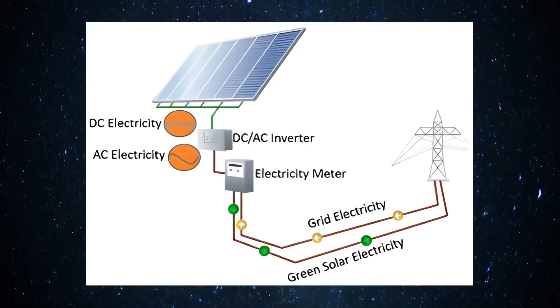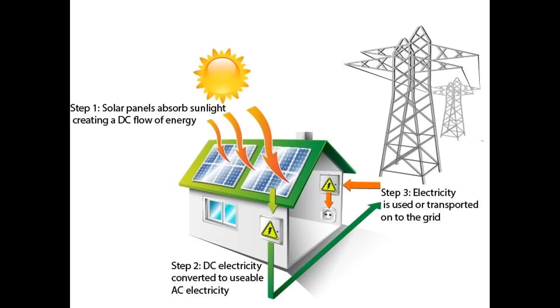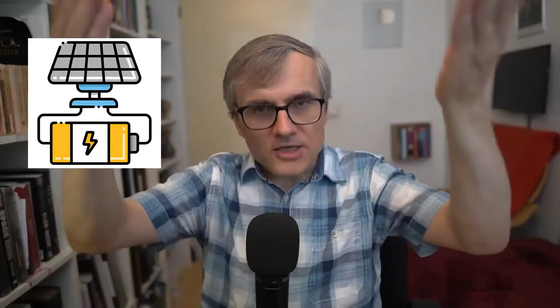In Romania, however, such solutions are expensive. To protect the network, a harsh method is applied, disconnecting the prosumer, if the prosumer, by delivering too much energy into the system, causes the voltage to rise in a dangerous way. The idea is as follows. Any solar panel produces direct current voltage. To feed it into the AC grid, an inverter is used. That's why the inverters used by prosumers have a built-in safety system. They monitor the electric voltage. When a lot of energy is fed into the grid and the electric voltage increases, the inverter automatically disconnects from the grid so that the high voltage doesn't cause any damage.